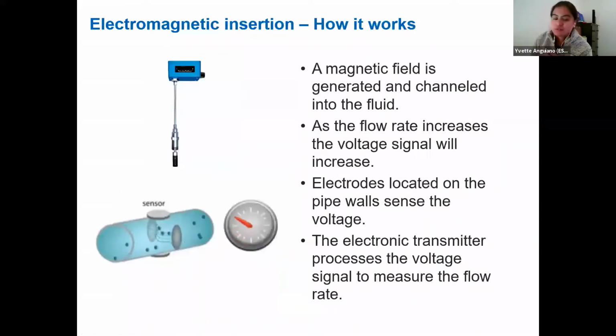So then going into using what he learned and how it works with this device. We were talking about how voltage is proportional to the movement of flow. And what is happening is that in this device, it generates a magnetic field within the liquid. And as the flow rate increases, the voltage signal increases. And electrodes located on the pipe walls read that voltage and process that signal into a flow rate.